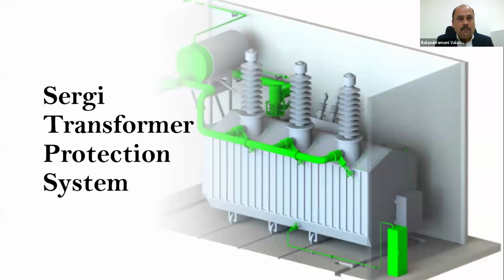The SERGI transformer protection system is basically used to protect the transformer. In general, if you have any problem with respect to the transformer, you have to protect it. You have Buchholz relays, pressure relief valve, HVREF, which is high voltage restricted earth fault, and low voltage restricted earth fault, to protect the transformer. But in case of a short circuit, when dielectric insulation rupture happens, it creates an arc. The transformer has a primary winding and a secondary winding, and the tank is filled with oil. Consider the tank, or the OLTC, on-load tap changer, or the cable box.